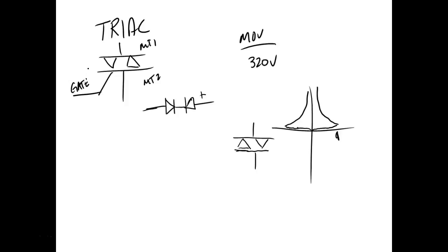So if you need extremely fast switching rates on the output of your PLC, you're not going to use relay outputs. If you want to control AC, you'll use it with a triac. A triac, you can blow those things if you exceed the breakover voltage too. So if you've got a relay output, odds are it's running AC, and there's a high probability you don't have to use any type of suppression circuits on relays.